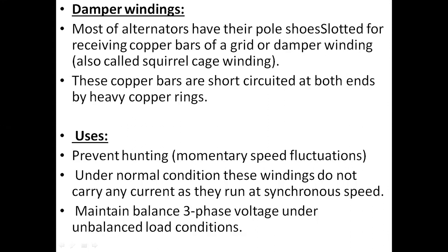Why do these turbo generators not have damper windings? Because the solid field poles themselves act as efficient dampers. Under normal running conditions, these damper windings do not carry any current because the rotor will be running at synchronous speed only. So these do not conduct any current. And they also maintain balanced three-phase voltage when there is any unbalanced load condition. Okay, so this is about the damper windings.